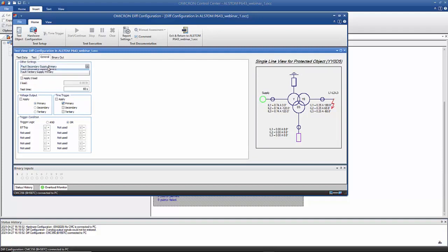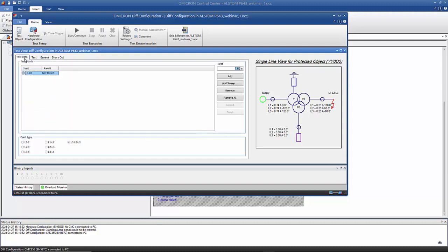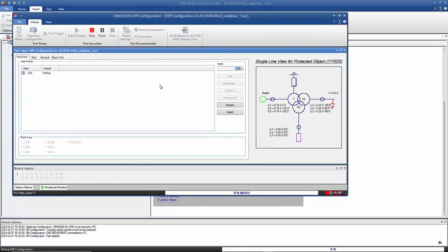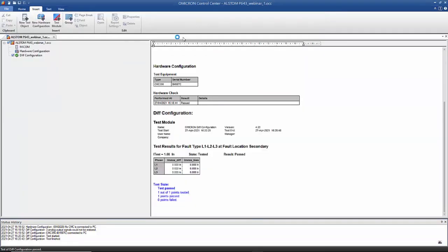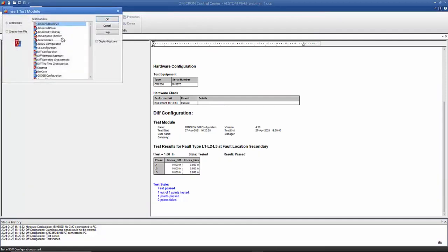as you see. And also you can play with the maximum time of the injection to get the chance to check the wiring by reading the relay measurement. And the most important thing, that relay will not issue any trip, because this is stable condition, and you have to press pass as indication that this test is already passed.